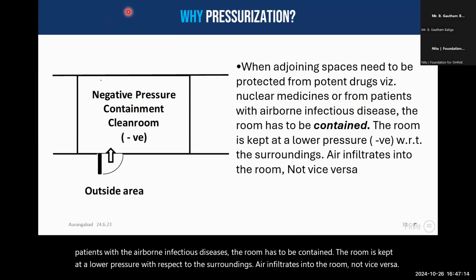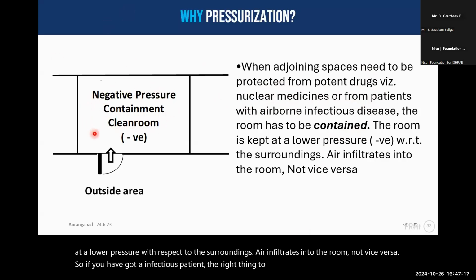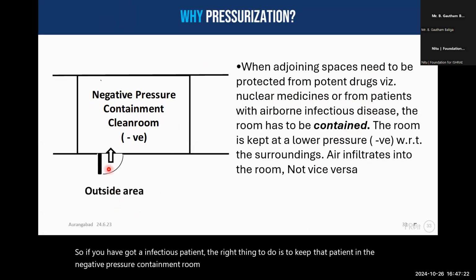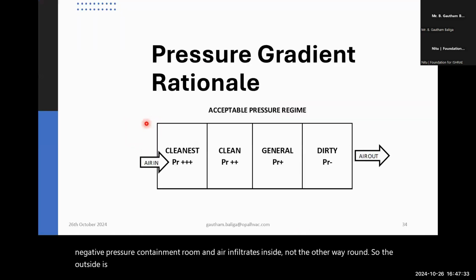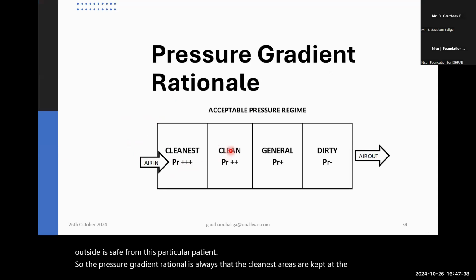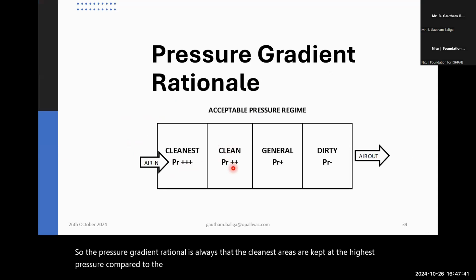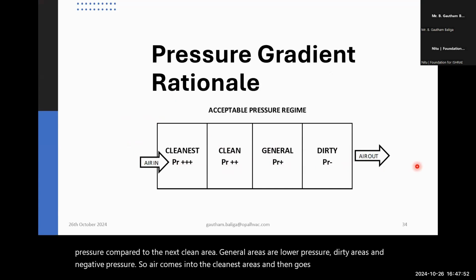So if you've got an infectious patient, the right thing to do is to keep that patient in the negative pressure containment room, and air infiltrates inside, not the other way around. So the outside is safe from this particular patient. So the pressure gradient rationale is always that the cleanest areas are kept at the highest pressure compared to the next clean area. General areas are lower pressure, dirty areas are negative pressure. So air comes into the cleanest areas and then goes out through the dirty areas.